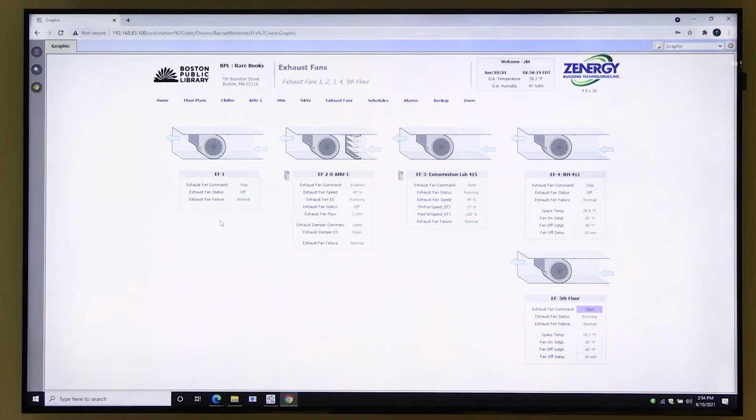Well, doesn't it have a local switch? That's what I'm asking, is it local? I think the determination during our discussions was that it would always be on because the chemicals are in the hood, so you always need that exhaust pulling out. Okay, so it's a 24/7 type of thing. We can make that determination too, we don't have to leave it on. It was just the engineers, maybe for safety reasons, were like, just do it this way. Typically on a lab exhaust system, yeah, because you're storing chemicals, you don't know when anyone's going to be using it.